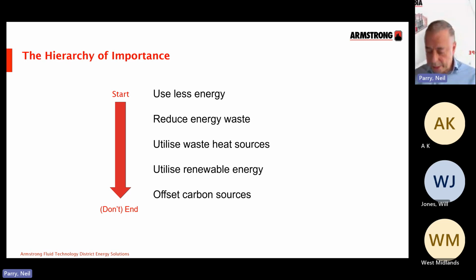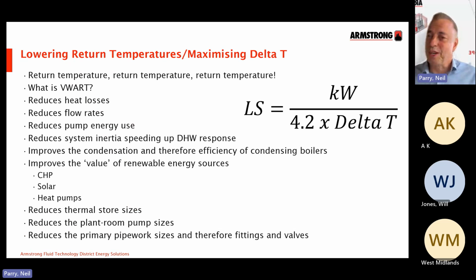So if you're a mechanical engineer, you've probably got that formula that you can see there tattooed on the inside of your eyelids. It basically shows you that the flow rate required equals the power required divided by your thermal transfer constant, 4.2, I've rounded it up slightly, multiplied by the delta T. So in terms of the kilowatts, as I mentioned earlier, we can address that in some way by that extra insulation, as an example, and reducing flow rates of taps, etc., etc.